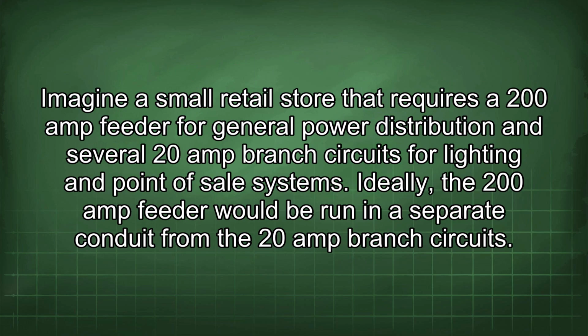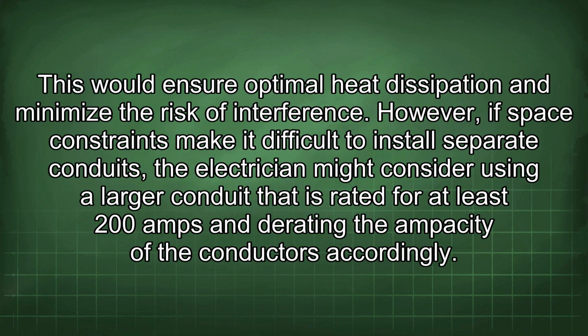Imagine a small retail store that requires a 200 amp feeder for general power distribution and several 20 amp branch circuits for lighting and point of sale systems. Ideally, the 200 amp feeder would be run in a separate conduit from the 20 amp branch circuits. This would ensure optimal heat dissipation and minimize the risk of interference.